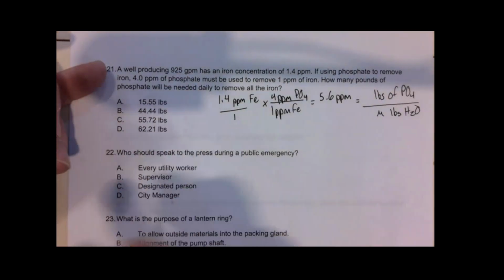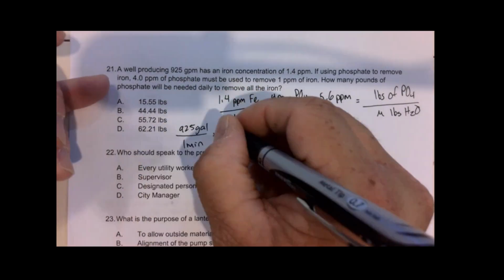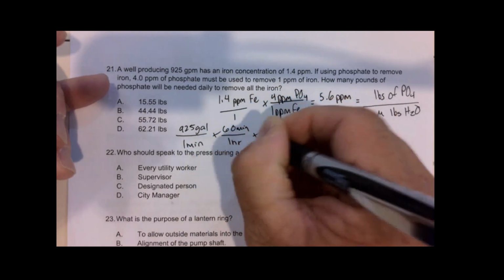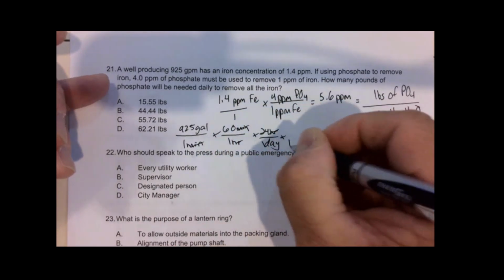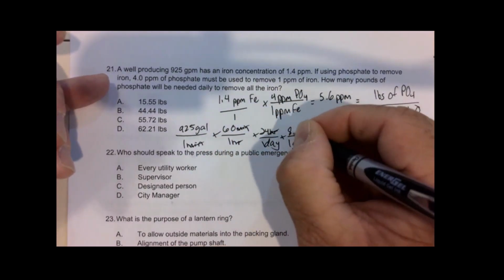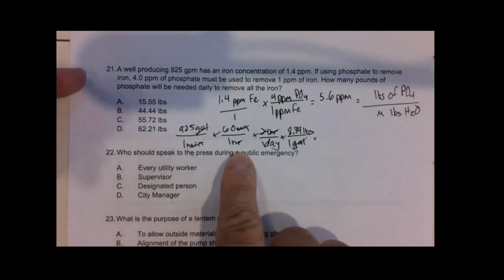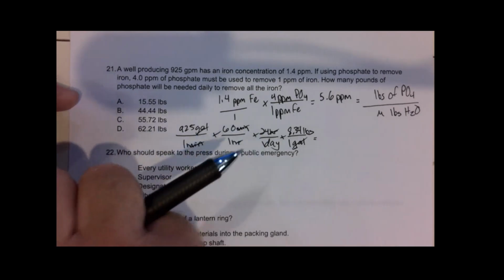Well, we're given a flow rate, so I need to convert this 925 gallons a minute, and so there's 60 minutes an hour, 24 hours to 1 day. And you see I got that to days. And I need to get gallons to pounds, 8.34 pounds per gallon. I wanted to write it out this time, all right? So you can see this is where the 1440 comes from. It's 24 times 60 for the minutes per day.